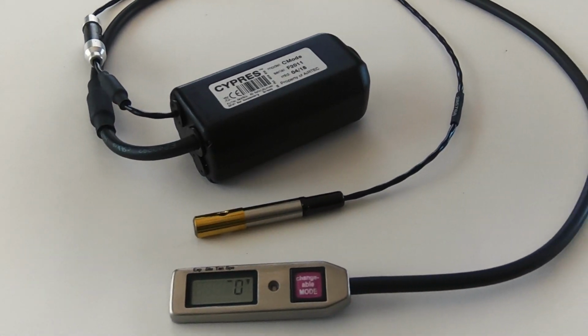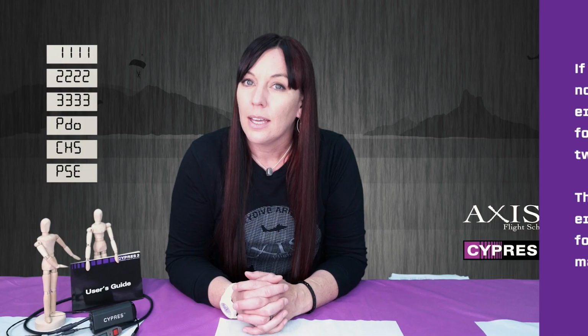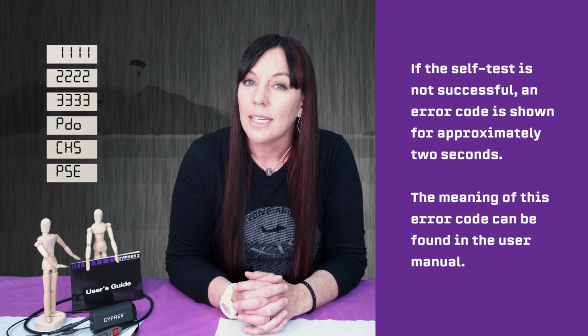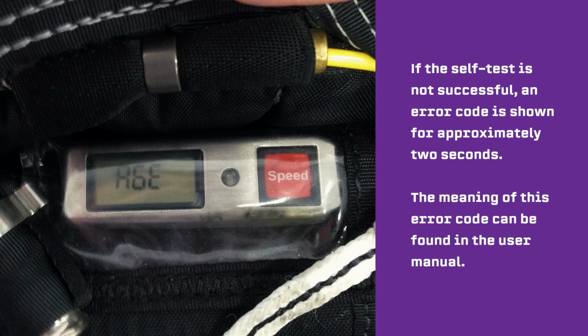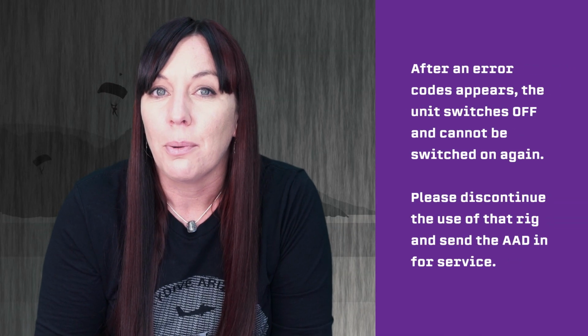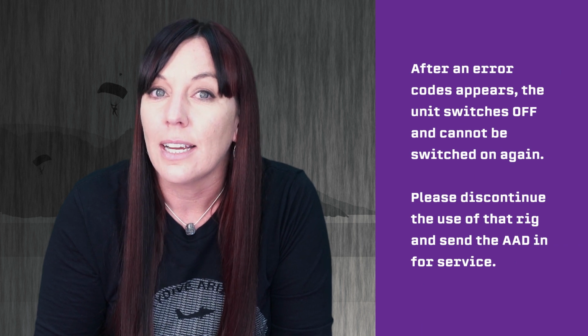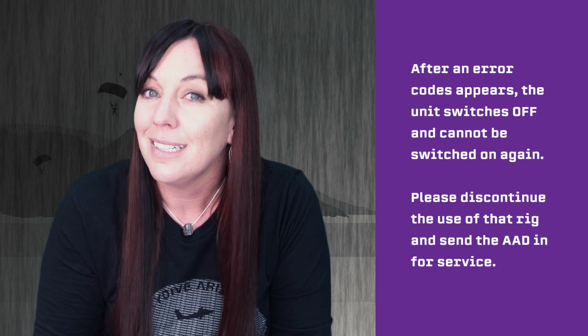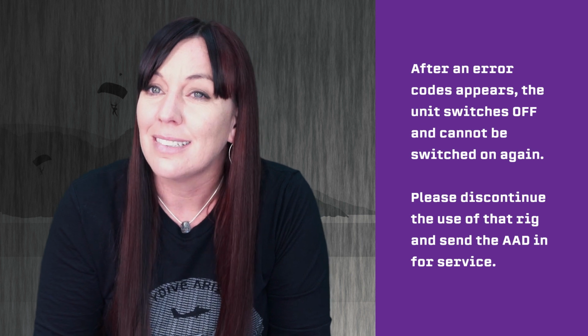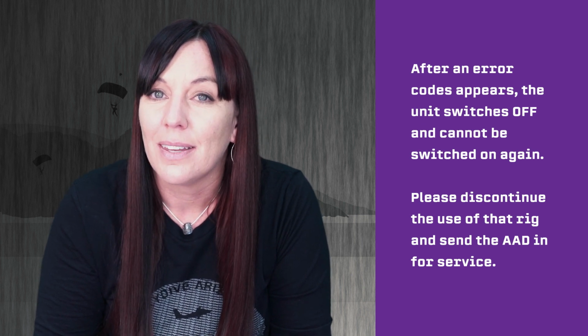When the 0 arrow down is shown, the unit should be functional for the next 14 hours. After 14 hours have passed, the unit will switch itself off automatically. If the self-test is not successful, an error code is shown for approximately 2 seconds. The meaning of this error code can be found in the user manual. After an error code appears, the unit switches off and cannot be switched on again. Please discontinue the use of that rig and send the AAD in for service.